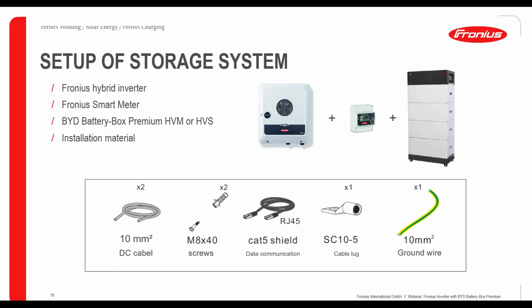Furthermore, of course, you need some installation material, and therefore we recommend that you use the DC cabling, for example, in this case, the 10 square millimeter DC cabling, of course, for DC plus and DC minus power connection from the inverter to the battery system. Furthermore, you get delivered some screws for fixing the battery modules to the wall so that no tilting is possible. Furthermore, you need some Cat5 shielded cable. In this case, we recommend that you just use the RJ45 standard, so Cat5 cable, for data communication between the Fronius inverter and the battery system.